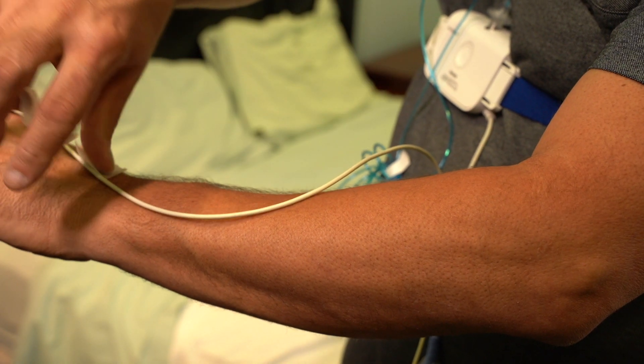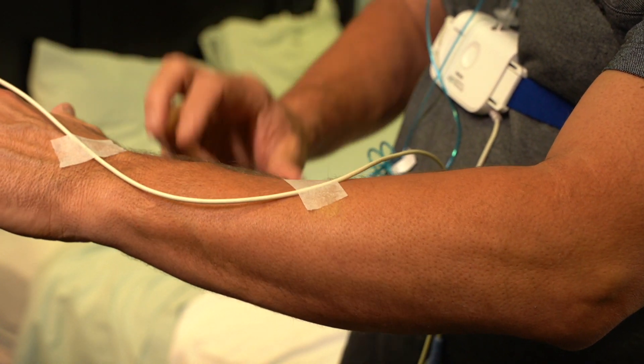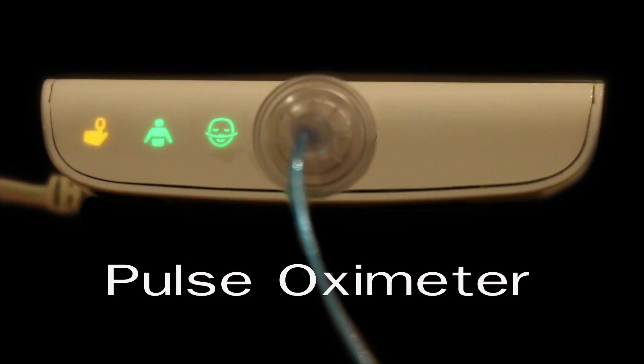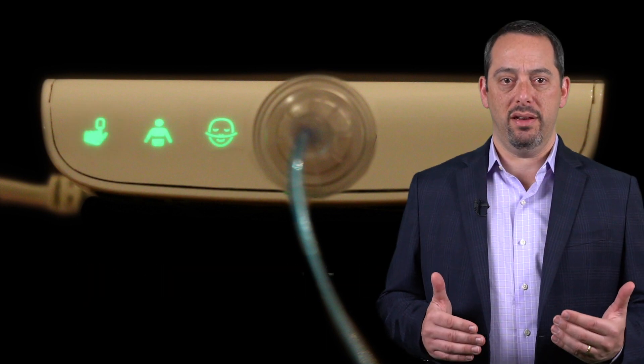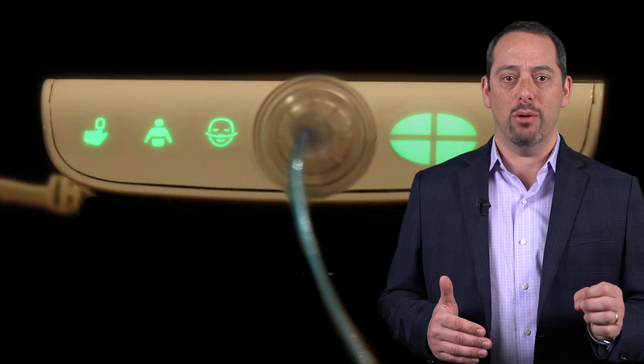Also, place two pieces of adhesive tape onto the arm where the cable is. We want the pulse oximeter to stay on your finger throughout the night. After several breaths with the pulse oximeter on, the pulse ox icon should start flashing yellow and then finally turn green. Once all the sensors have been connected and the device is getting good signals, all the icons are now solid green.